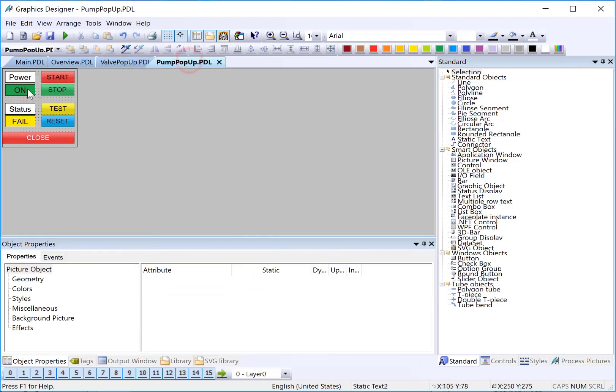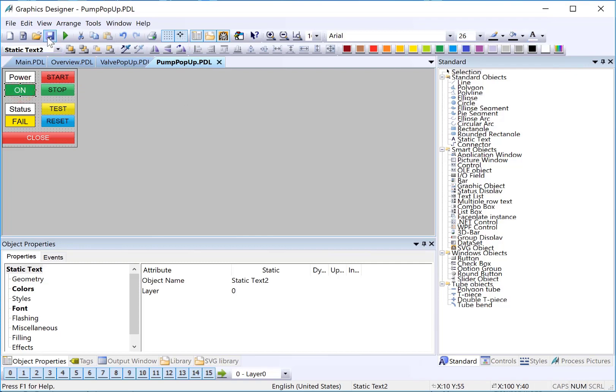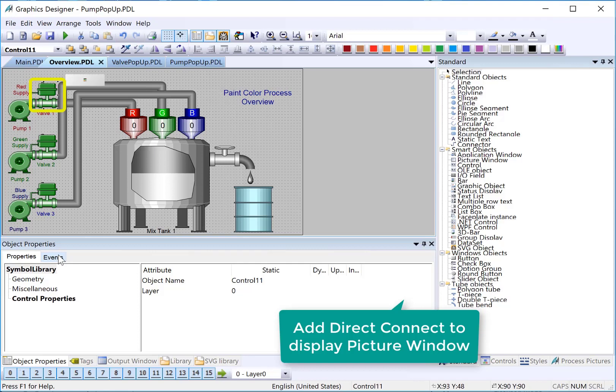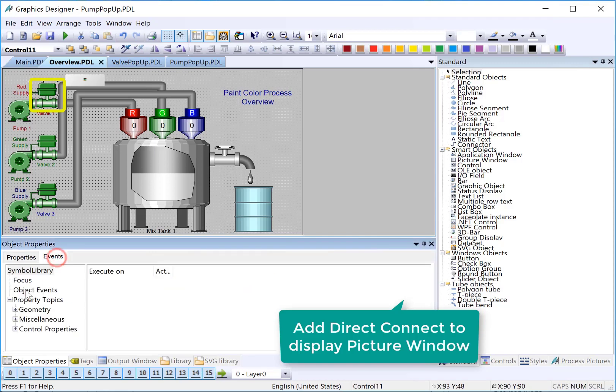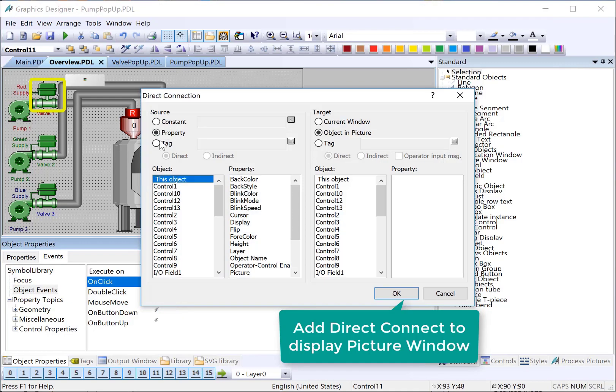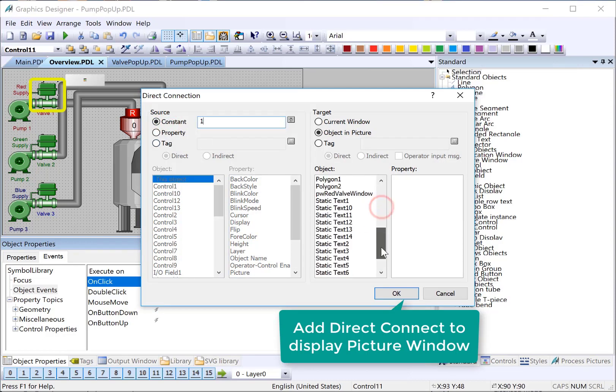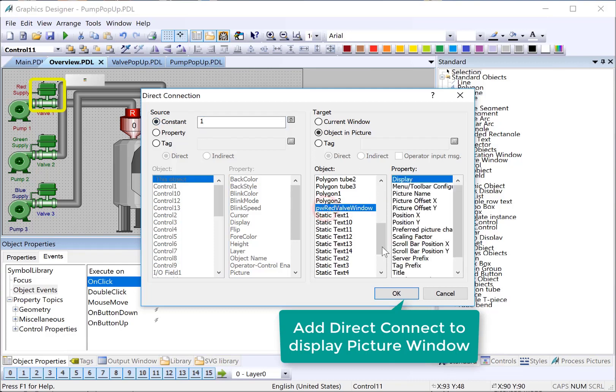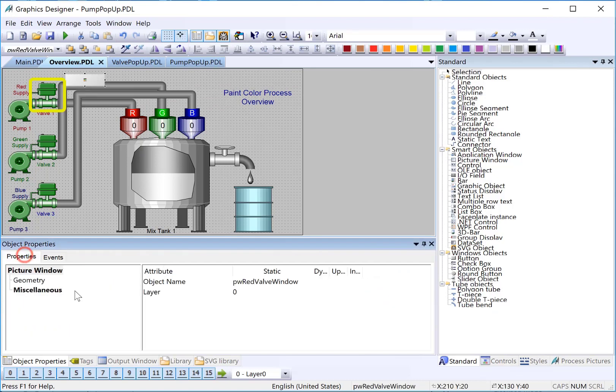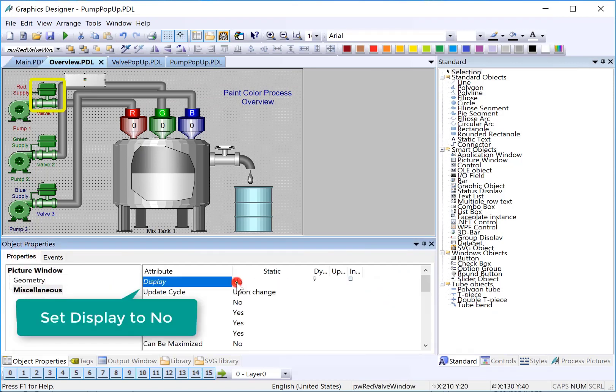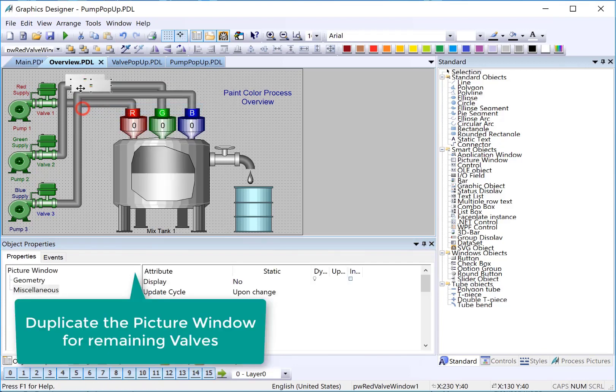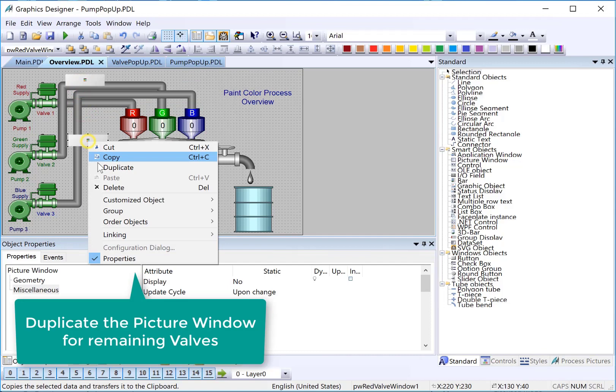And then go back to overview. On the valve, we're going to use a direct connect to turn on the display of that picture window. We'll just put a constant one. And since we gave it a good name, picture window red valve window, we will just put a one into the display property. Then, by default, on here, we'll just turn off the display so it doesn't come on automatically. And notice that display is italicized. That's because the direct connect is now controlling that. Now, we just have to duplicate this for each of our valves.